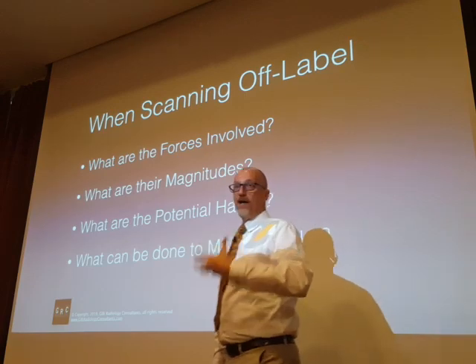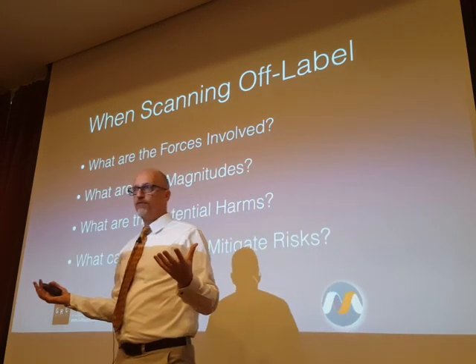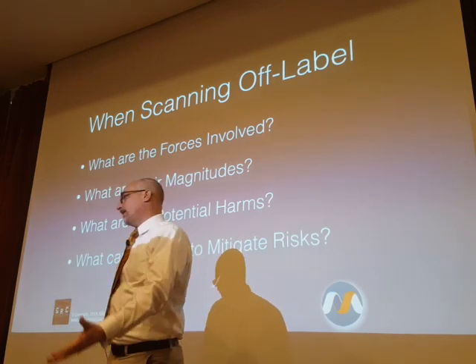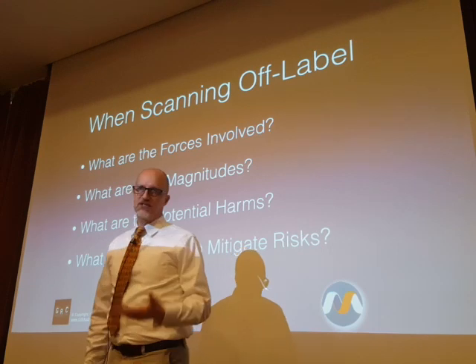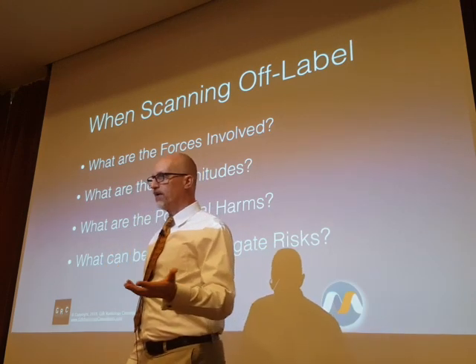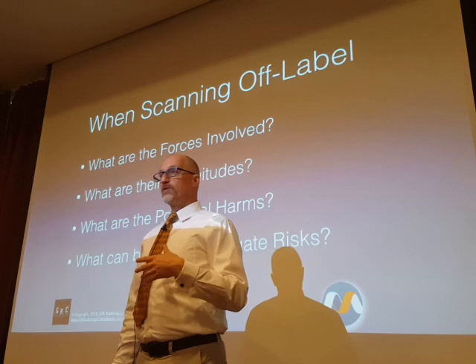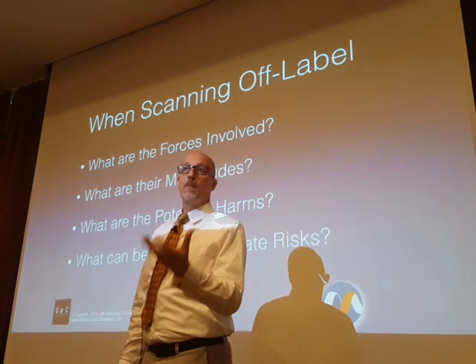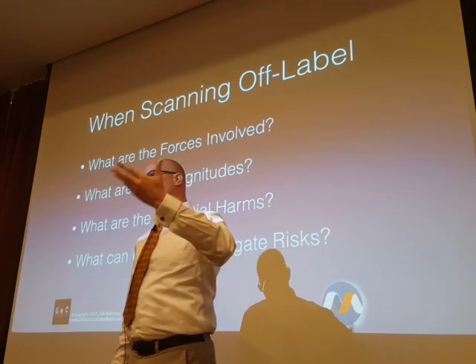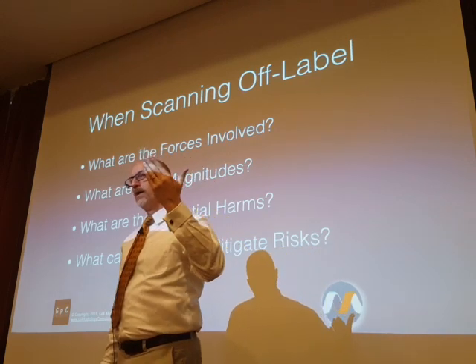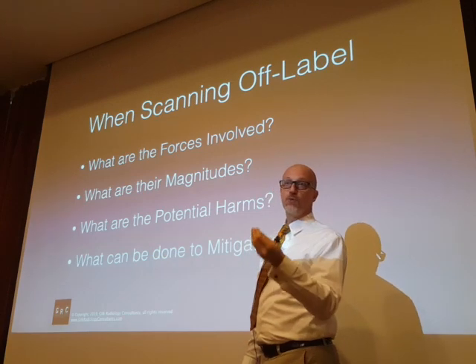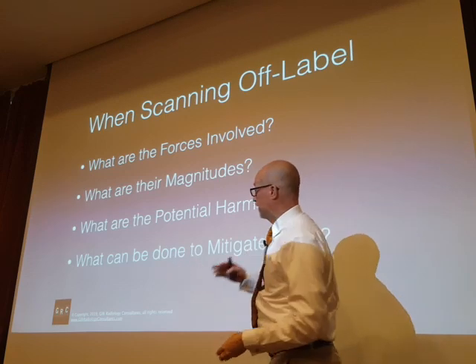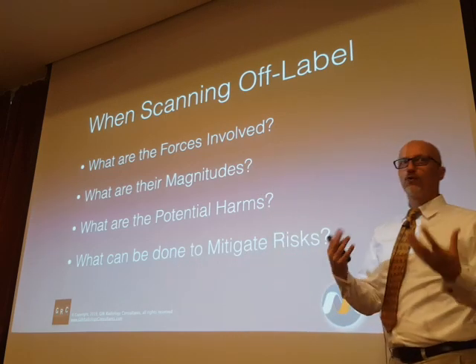We do not care what the maximum potential value is for a scanner. If you have an implanted device that says 720 gauss per centimeter, but your system goes up to 1,100 gauss per centimeter — that doesn't matter. It doesn't matter what the maximum for the system is. What matters is what the implant or device will actually be exposed to. Understanding that spatial distribution and those values is incredibly important.